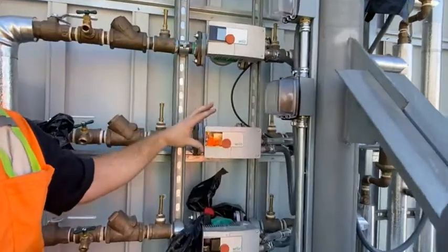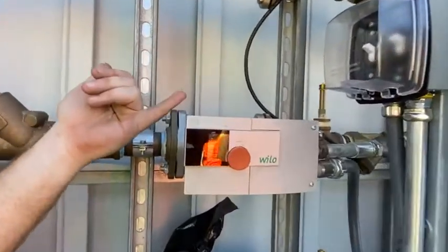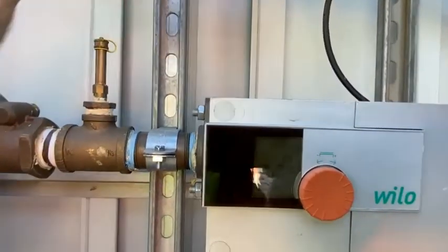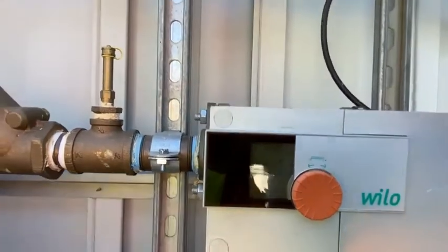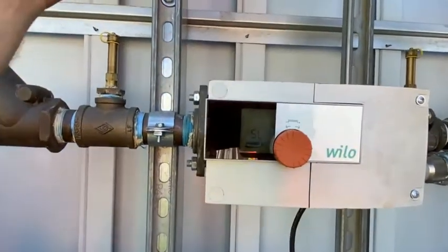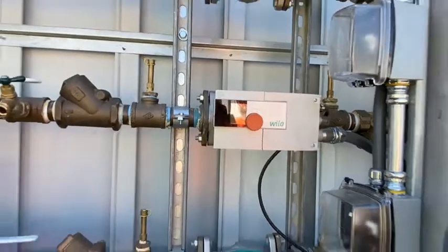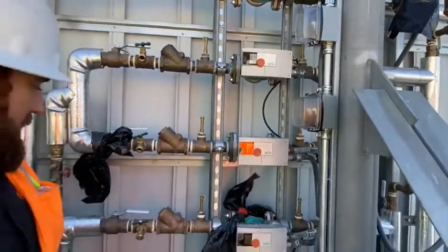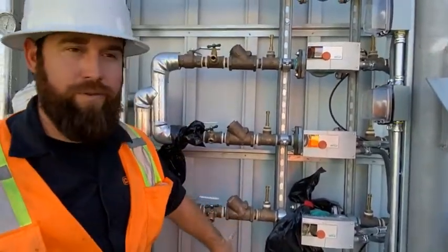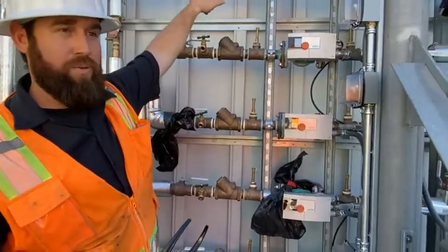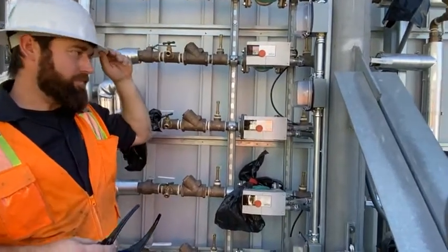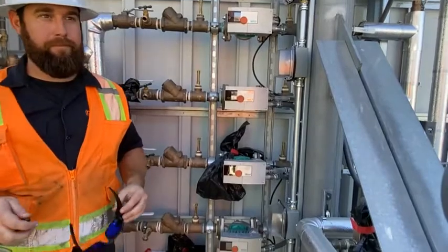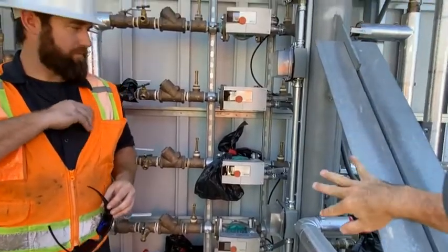These are set to rotate operation every 24 hours of runtime, so only one of these pumps is going to be running at a time. Same with these ones. This one's going to be running almost continuously, just because it's standalone. These two we got are the 140 return. These three are the 120 returns. Remember the upper ones, the non-kitchen. We have kitchen return and then the kitchen 140.